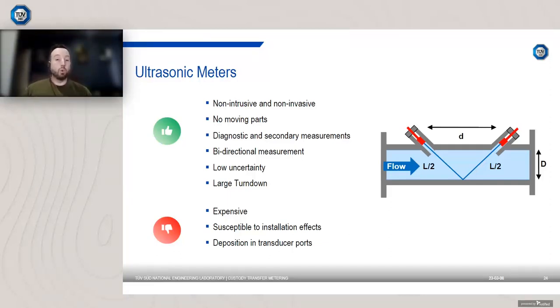They typically have quite a low uncertainty, so 0.1% or even better, depending on how you calibrate them, and they have a large turndown. Now, turndown varies depending on which manufacturer you speak to. Some will claim thousands to one turndown, but typically they have a larger turndown than the more traditional measurement technologies. Now, what are the downsides to ultrasonic meters? Well, typically they're quite expensive devices, and again, like orifice plates and turbine meters, they're susceptible to installation effects.